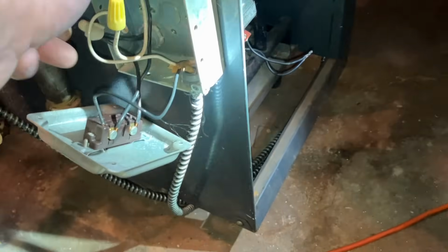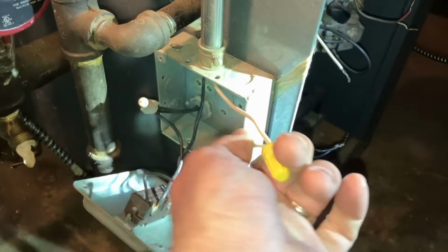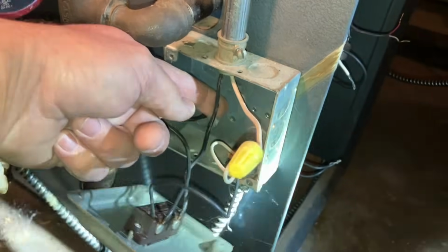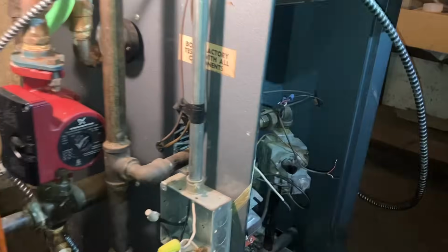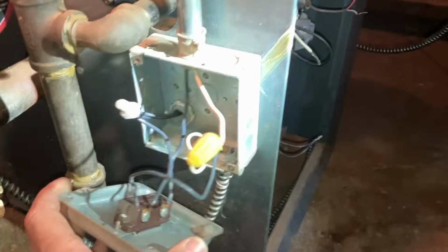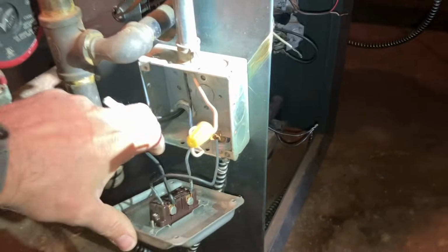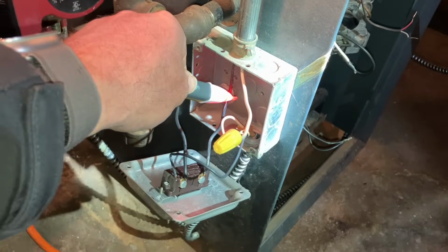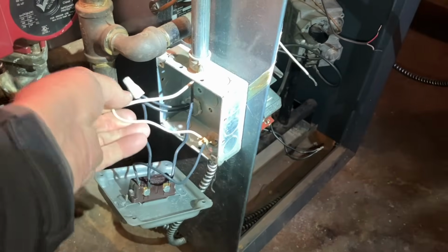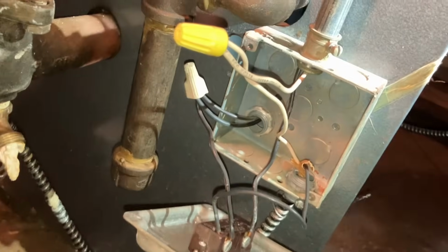All right, let's take a look here. We have line, probably L1. And this is neutral coming from our power source above, which goes there. And that's probably going to the switch at the top of the stairs and/or the circuit breaker panel. So this is line. And let's verify we have power there. Okay, so power's on this line. And this is our neutral. Now, there's that one we're trying to figure out.